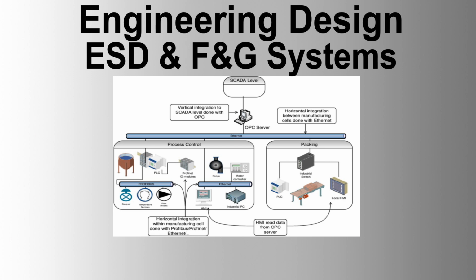2. F&G functional requirements. Early detection of hazardous atmospheres. Initiate visual and audible alarms on the platform and in the main control room. Isolate the source of the hazard and all sources of ignition. Initiate extinguishment systems where applicable. Implement plant shutdowns and blowdowns where necessary. Provide visual alarms, beacons, in high-noise areas.